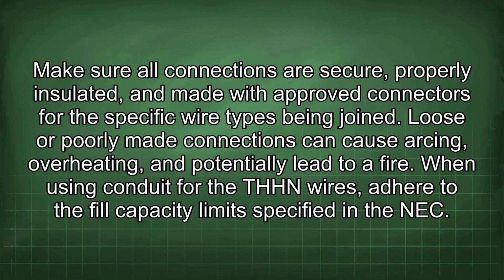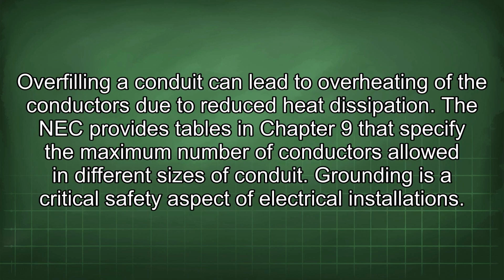When using conduit for the THHN wires, adhere to the fill capacity limit specified in the NEC. Overfilling a conduit can lead to overheating of the conductors due to reduced heat dissipation. The NEC provides tables in Chapter 9 that specify the maximum number of conductors allowed in different sizes of conduit.